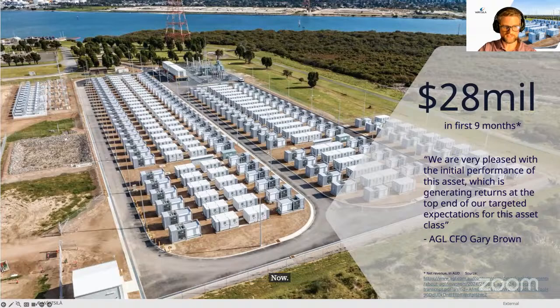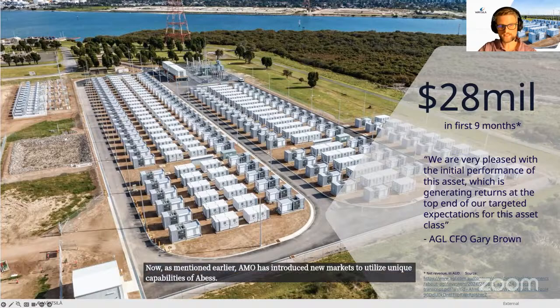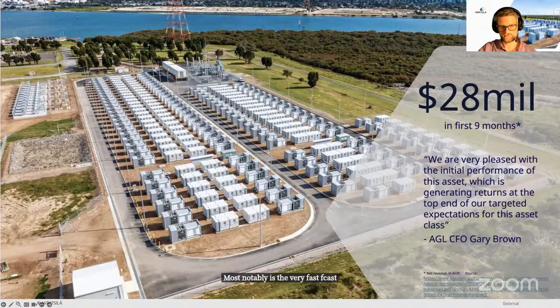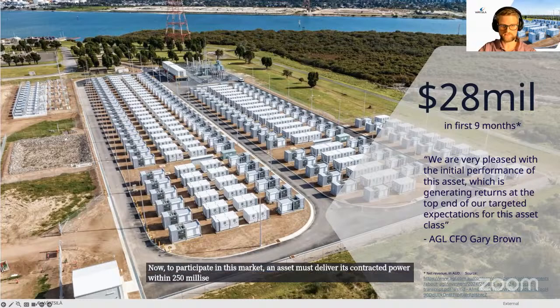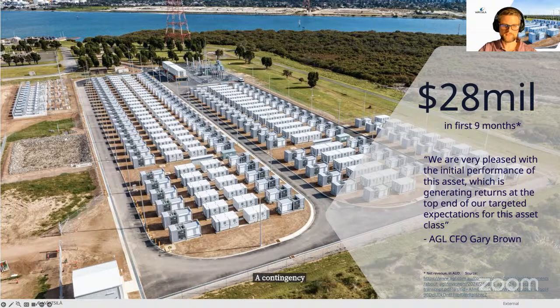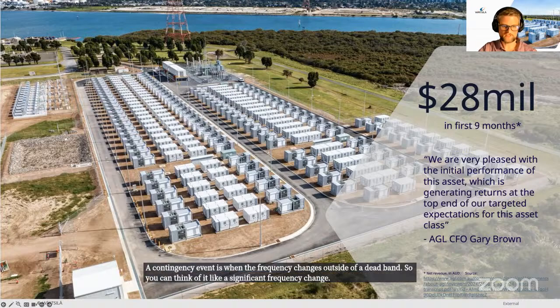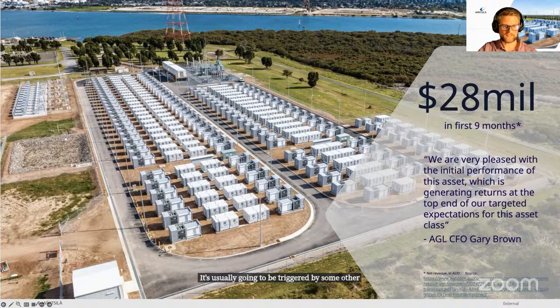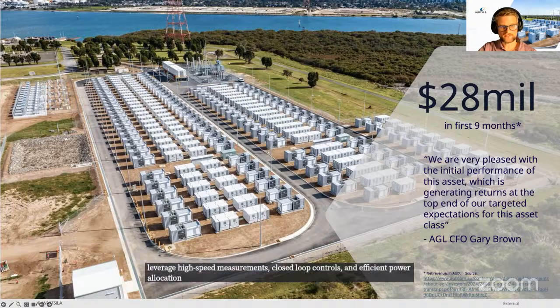It's located in Australia and began commercial operation in the second half of 2023. As mentioned earlier, AEMO has introduced new markets to utilize unique capabilities of a BESS, most notably the very fast FCAS frequency response market. To participate, an asset must deliver its contracted power within 250 milliseconds of a contingency event. A contingency event is when the frequency changes outside of a deadband - a significant frequency change, usually triggered by some other plant tripping offline, either a load or a generator.